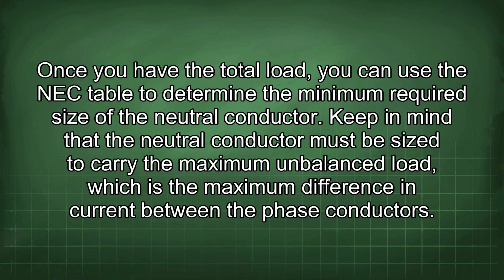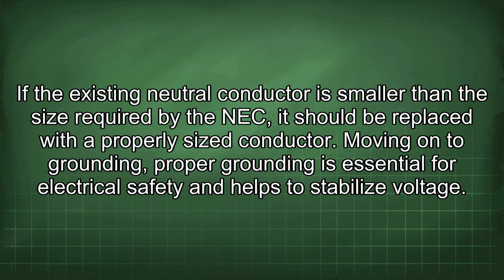Once you have the total load, you can use the NEC table to determine the minimum required size of the neutral conductor. Keep in mind that the neutral conductor must be sized to carry the maximum unbalanced load, which is the maximum difference in current between the phase conductors. If the existing neutral conductor is smaller than the size required by the NEC, it should be replaced with a properly sized conductor. Moving on to grounding.